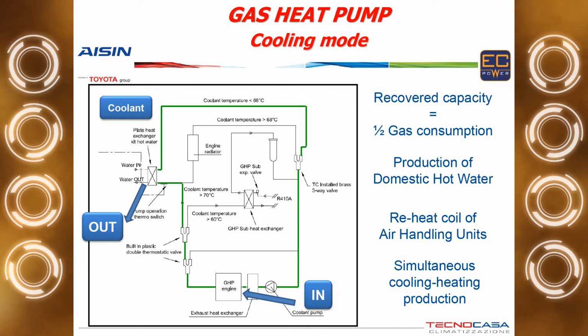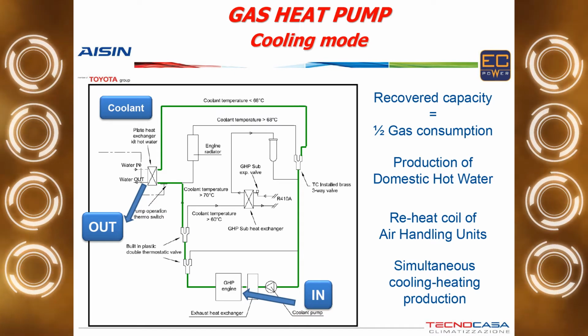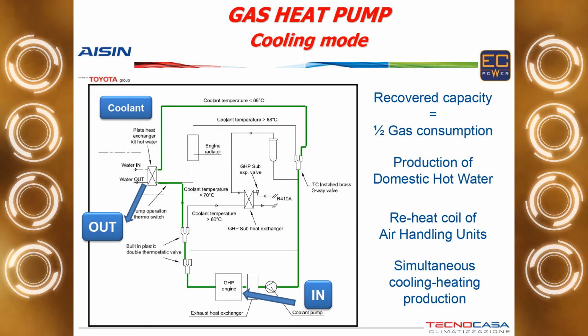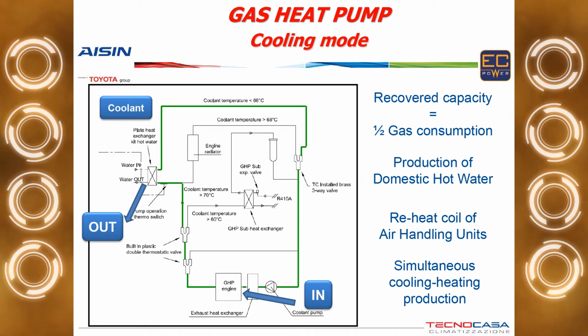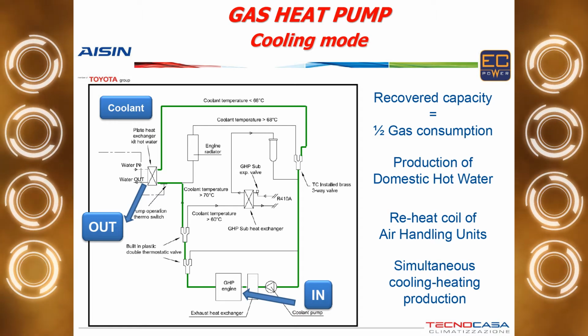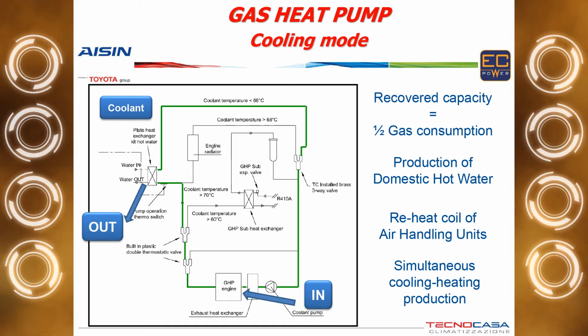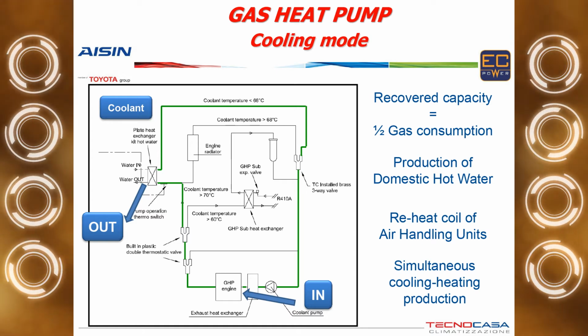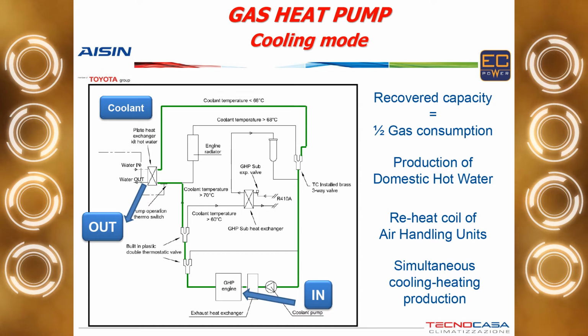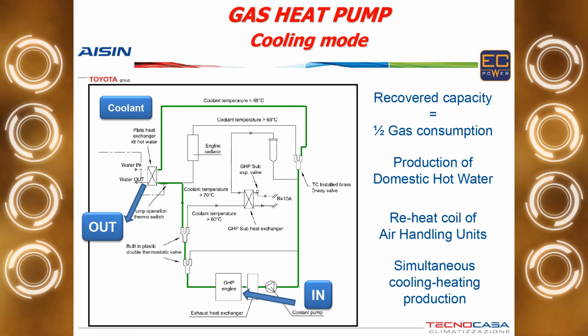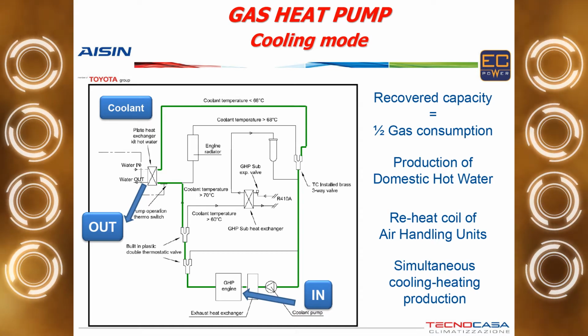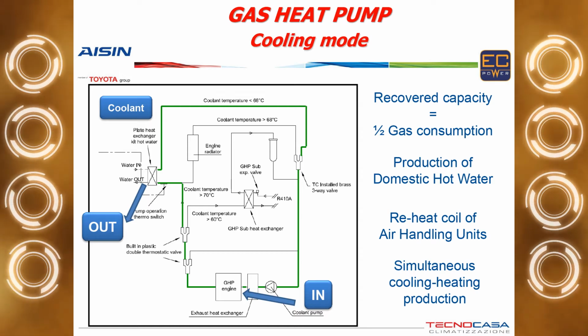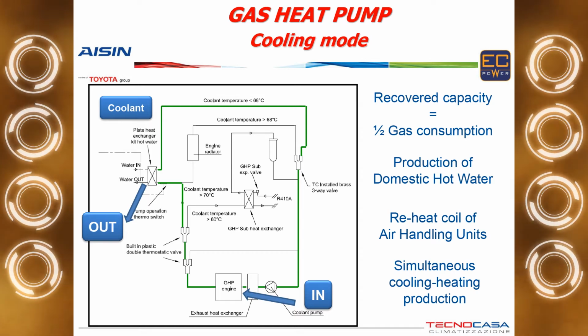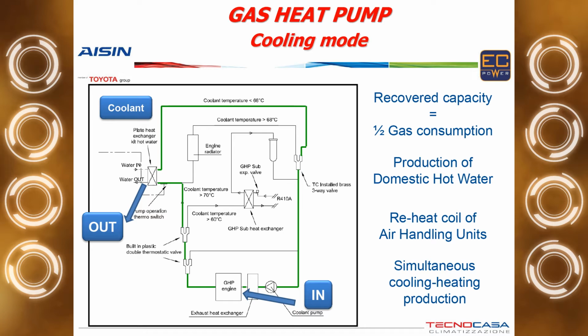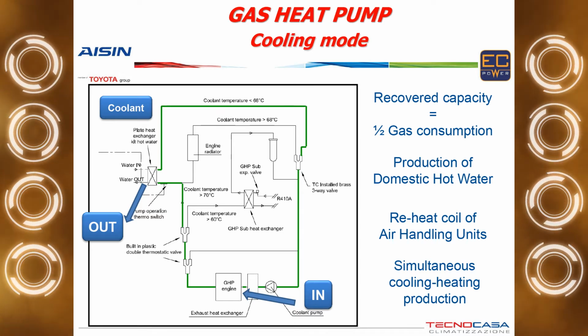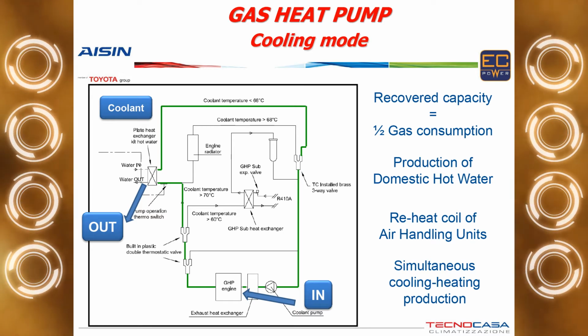It seems that there is no use for the combustion heat, which is not true because since you have an engine, you also have a second circuit, which is the engine coolant circuit. We use this engine coolant circuit, which is equipped with a double thermostatic valve, to cool down the engine, of course, but also to produce the domestic hot water. Since the engine needs to be cooled down, at some point during the operation, the coolant temperature is higher than 70 degrees Celsius.